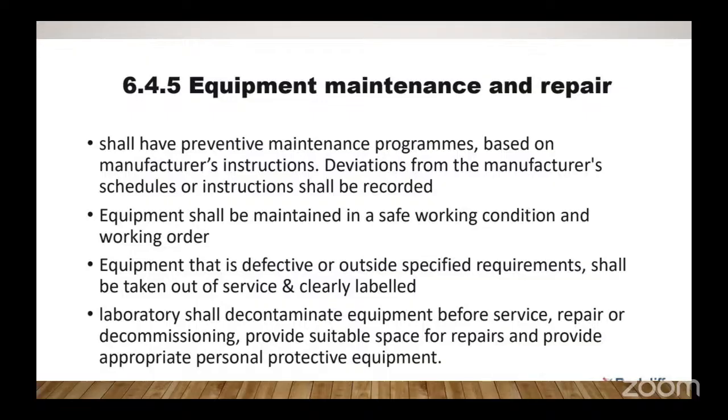Equipment that is defective or outside specified requirements shall be taken out of service and clearly labeled. The laboratory shall decontaminate equipment before service, repair, or decommissioning, provide suitable space for repairs, and provide appropriate personal protective equipment.